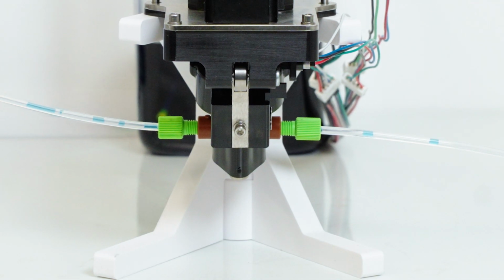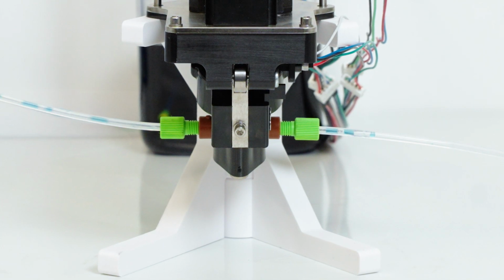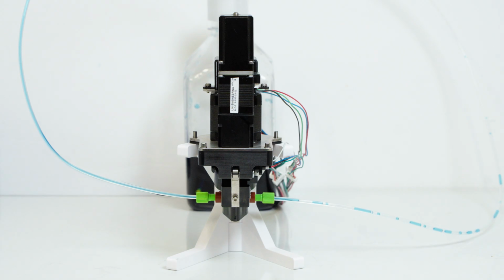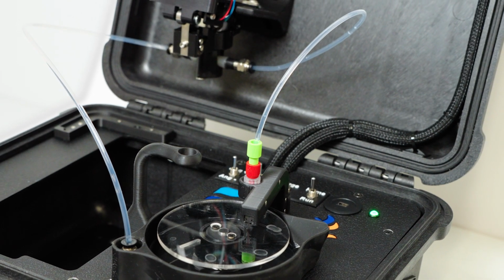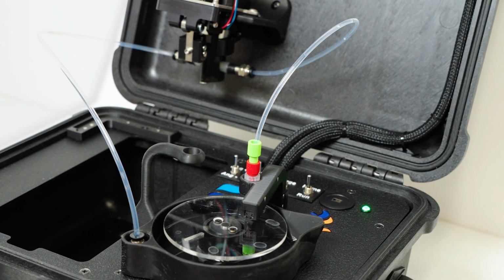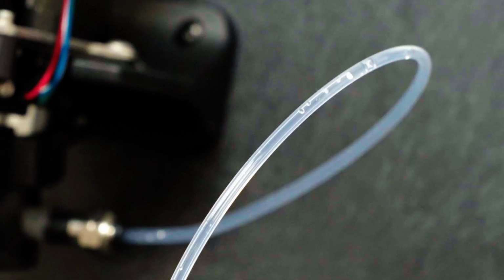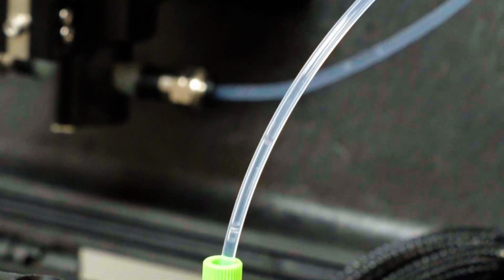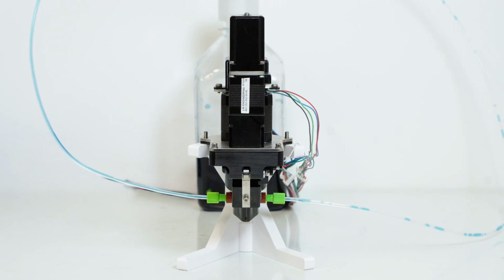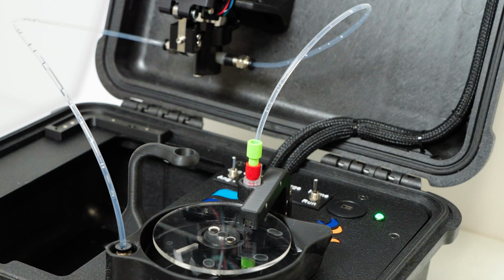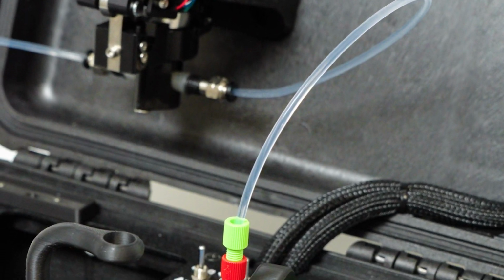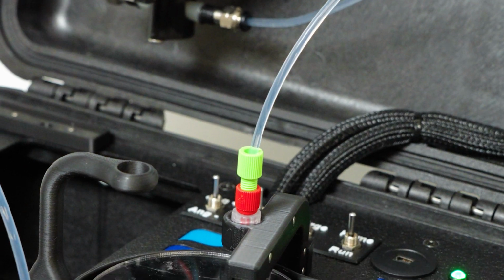Next, let's talk about priming, because proper priming is essential for accurate and consistent pump performance. Priming removes air from the pump head and the fluidic lines. Even a small amount of microbubbles can have an effect on precision and accuracy, especially in microdosing applications. Each fluid metering pump may require a slightly different priming approach depending on the model and the overall system setup. So instead of relying on one universal procedure, it's important to focus on the end goal, a clean, air-free fluid path. For our STF and Phoenix style pumps, a basic priming method is to start by running at a faster speed to fill your lines, then reduce the speed to push out any remaining air. Repeating this process can help achieve a stronger prime, though it's not always necessary. A well-primed system will deliver smoother operation, more repeatable performance, and far more reliable accuracy overall.